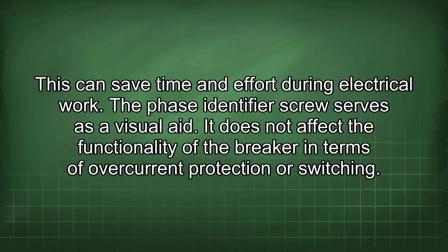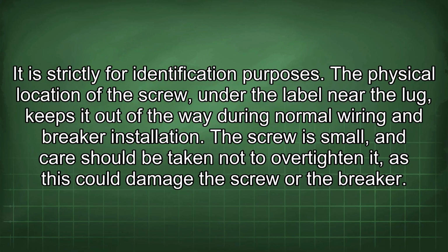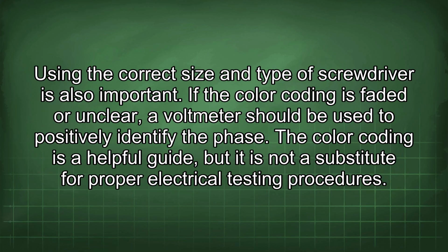The phase identifier screw serves as a visual aid. It does not affect the functionality of the breaker in terms of overcurrent protection or switching. It is strictly for identification purposes. The physical location of the screw, under the label near the lug, keeps it out of the way during normal wiring and breaker installation. The screw is small, and care should be taken not to over-tighten it, as this could damage the screw or the breaker. Using the correct size and type of screwdriver is also important.